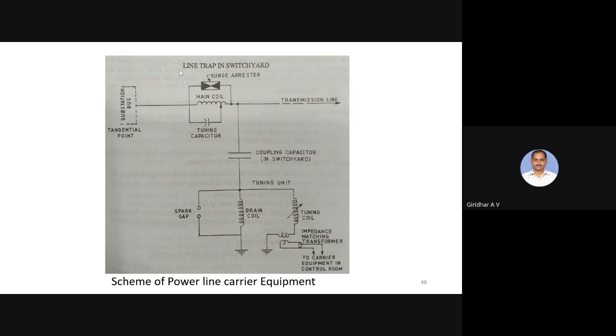So in the power lines, these high frequency signals, carrier communication, everything will be transmitted through the power lines. So you can see different components here in these power line carrier equipment. Coupling capacitor, you can see. Usually these coupling capacitors offer low reactance to carrier frequency and high reactance to power frequency, so that only the information will be allowed in. The carrier frequency signals will be allowed into the carrier equipment, and because it offers high reactance, it won't allow the power frequency of 50 Hz.